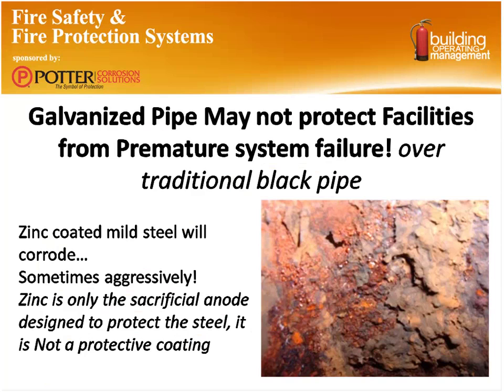The trouble is once that zinc is gone from the inside of the pipe, it can actually accelerate the corrosion, because the zinc doesn't equally dissipate from the whole pipe. It's spotty. And once you create a breach in the zinc, that particular point is going to corrode that much faster. So we've actually seen systems where galvanized pipe in pre-action systems and dry systems has failed faster than traditional black pipe. The other thing to look out for are some of the thin wall pipes that were used more prevalently, and still in some cases today, that can cause those failures to happen in a rapid duration.